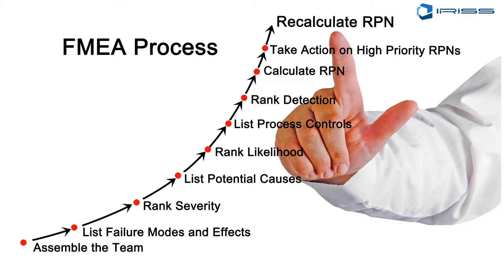You assemble a cross-functional team and look at the critical pieces of the electrical and electromechanical infrastructure. You list the possible modes of failure, the ways in which things can fail, and what the impact of a failure on each piece of equipment would be. You go through a ranking and severity exercise — would it cause 10% or 100% of the facility to be impacted? What are the safety implications? What are the environmental implications, such as a discharge of untreated wastewater? All of these things go into a rank severity exercise in the RPN process.